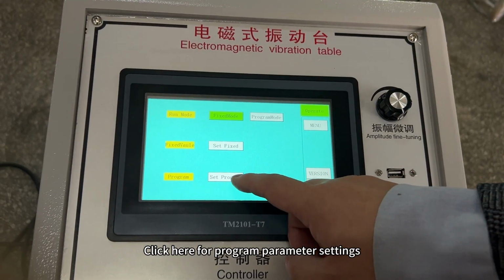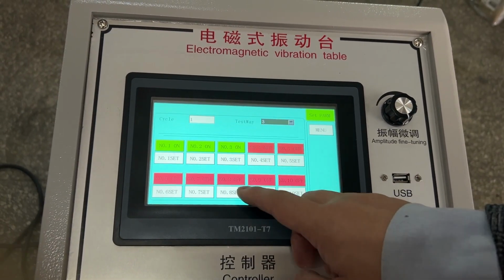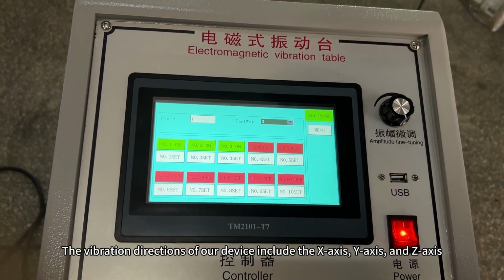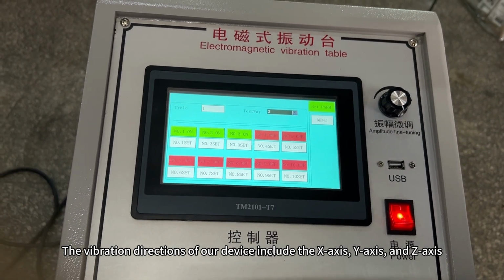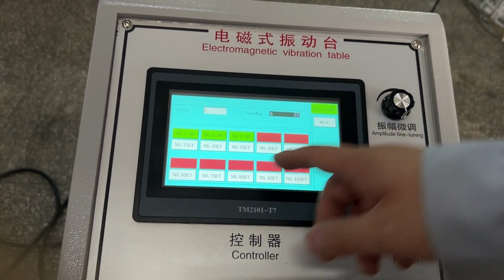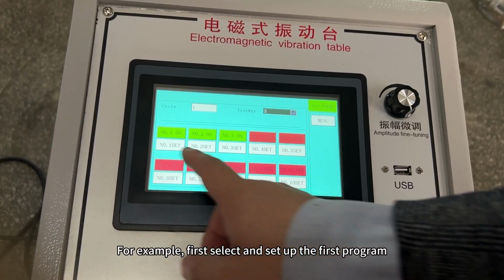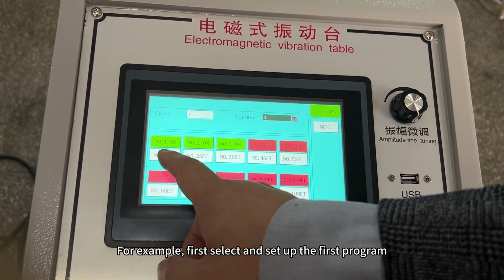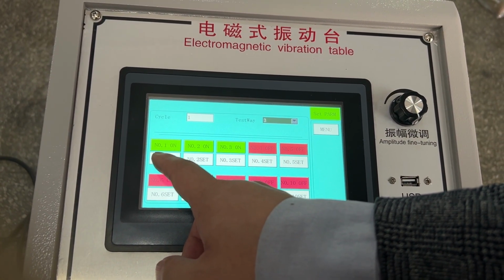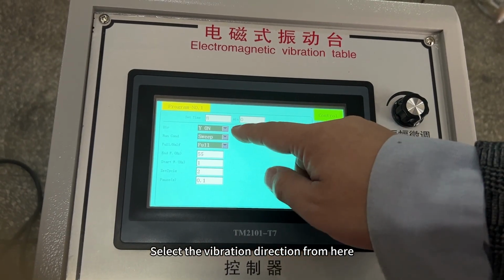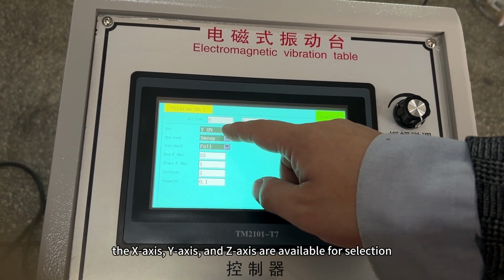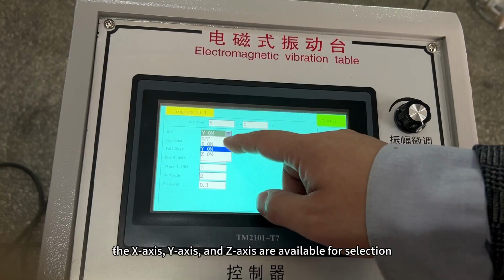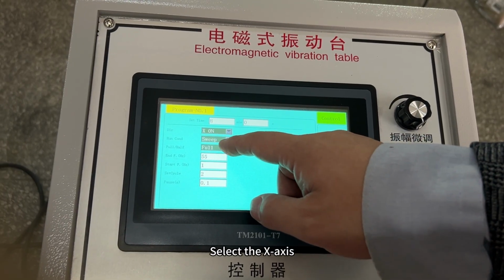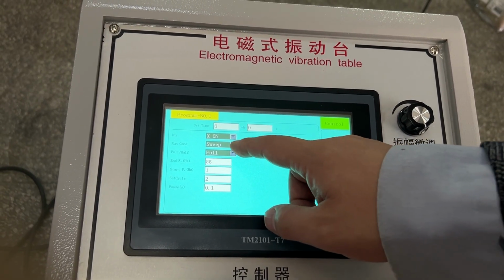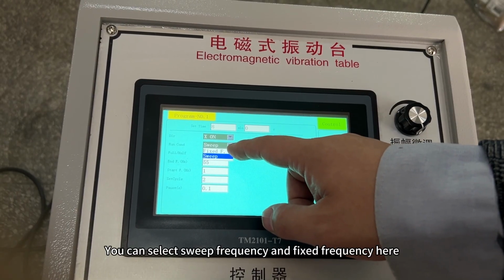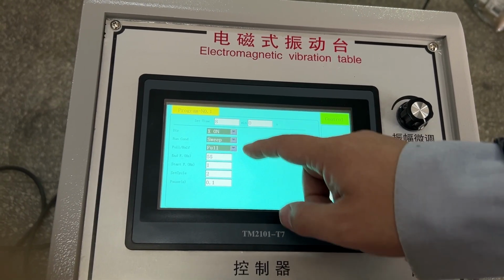Click here for program parameter settings. The vibration directions of our device include the X-axis, Y-axis, and Z-axis. For example, first select and set up the first program. Click here. Select the vibration direction from here. The X-axis, Y-axis, and Z-axis are available for selection. Select the X-axis. You can select sweep frequency and fixed frequency here.